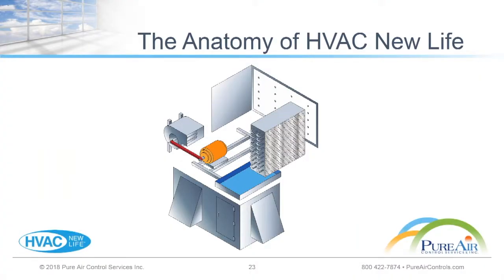So here's a diagram of the anatomy of an air handler. We're looking at four pieces that are pointed out as the final products once this process is completed. An environmentally clean coil from our Pure Steam process - that's number one. Then internal and external components coated with antimicrobial high performance coating - that's number two, referred to as Pure Coat. Then number three, referred to as Pure Liner, the drain pan after it's treated and de-rusted is coated with antimicrobial high performance flexible coating. And finally, the insulation is replaced with the Pure Cell, as I mentioned before. So this gives you, looking down on the air handler, what's going on here when we're talking about HVAC New Life from the hygienic perspective of restoring the unit.